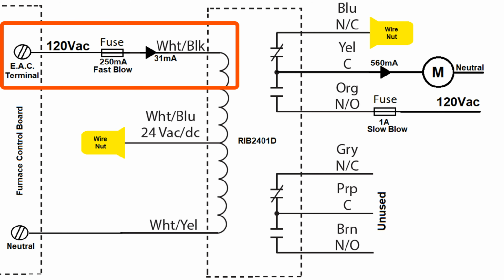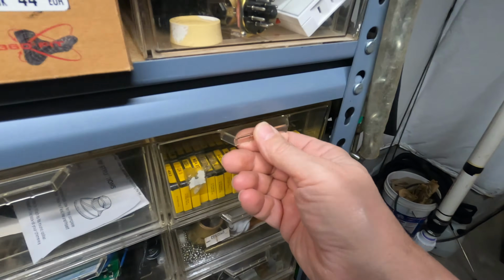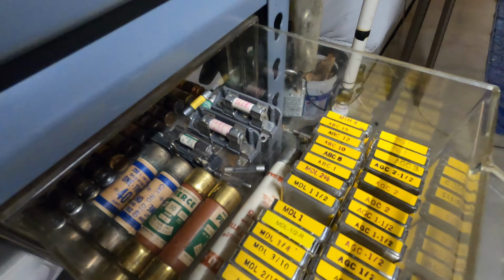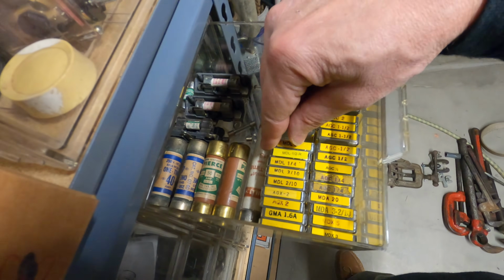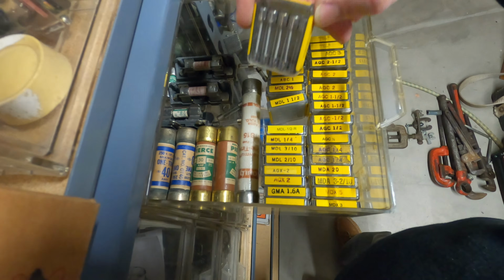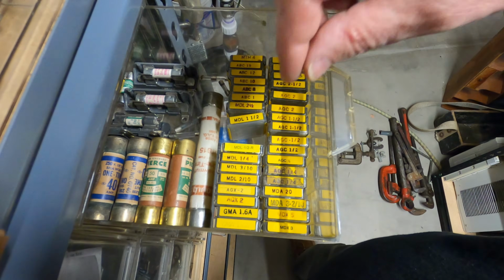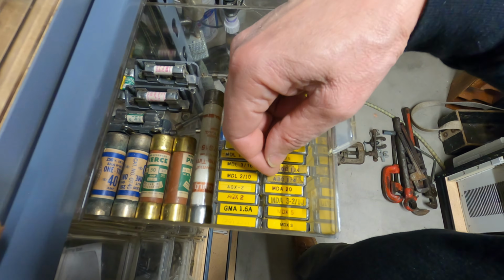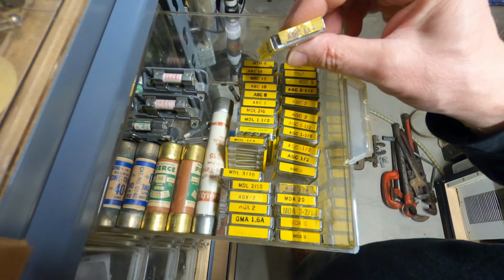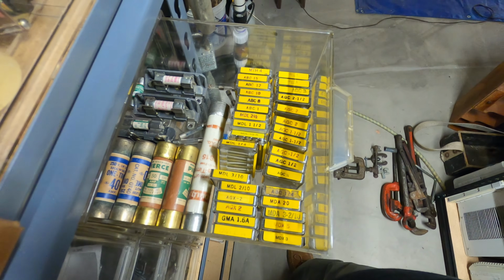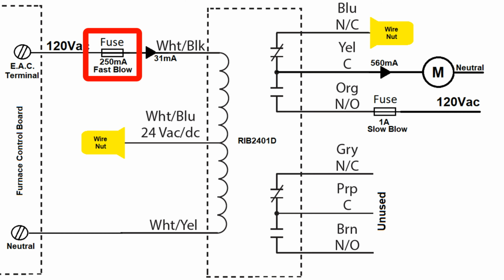Why did I use a 250 milliamp fuse? Well, it's because I happen to have an abundance of them in stock. MDL1. So why spend $5 to $10 for a box of 100 milliamp fuses? AGC 1/4. A 1/4 amp fuse will certainly protect a 1 amp rated circuit. The fuse on the EAC signal needs to protect the circuit from a short circuit at 1 amp or less.